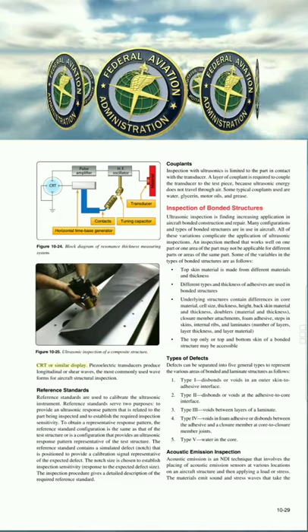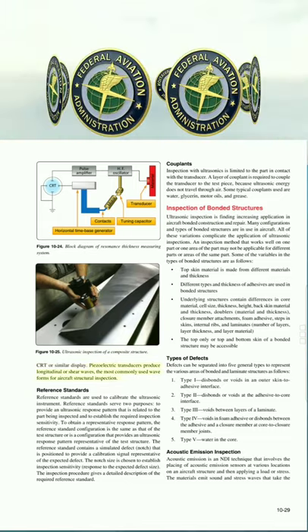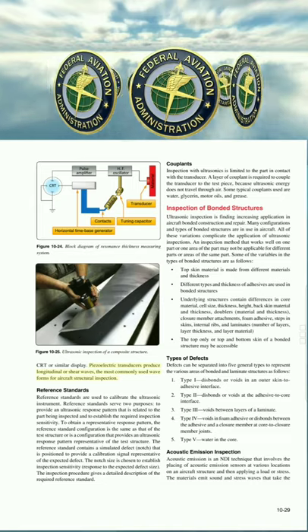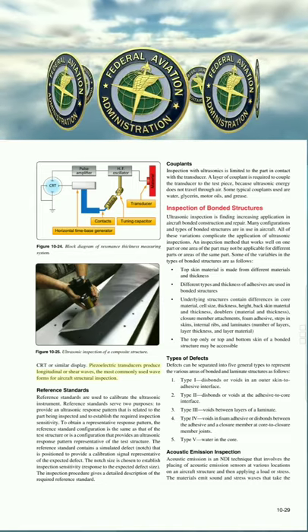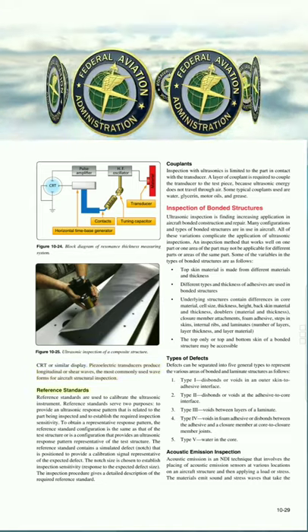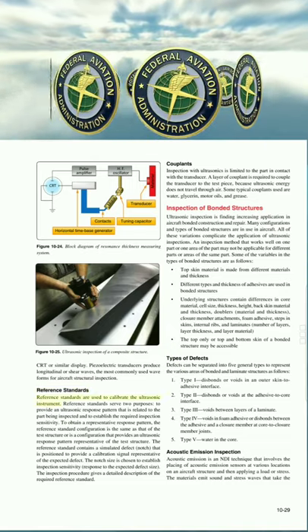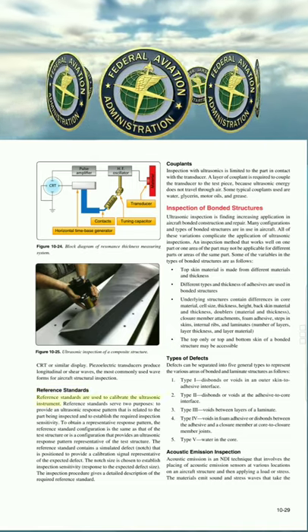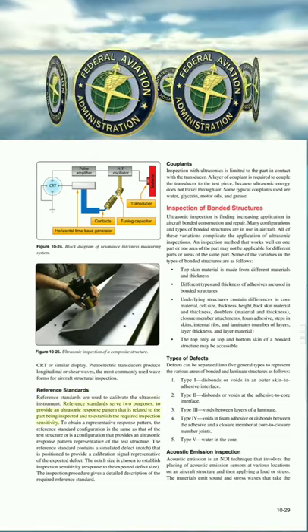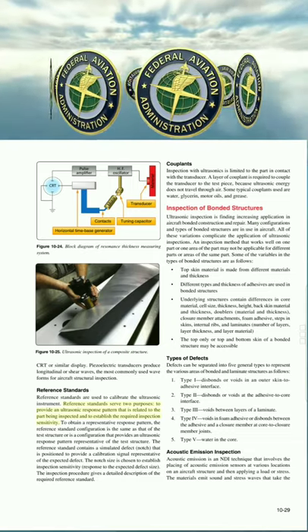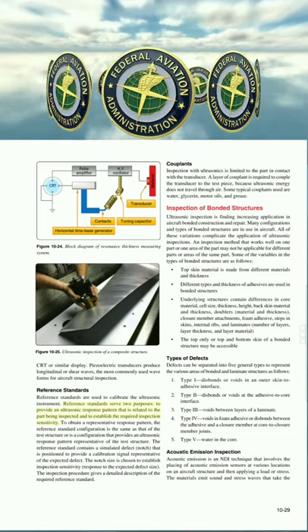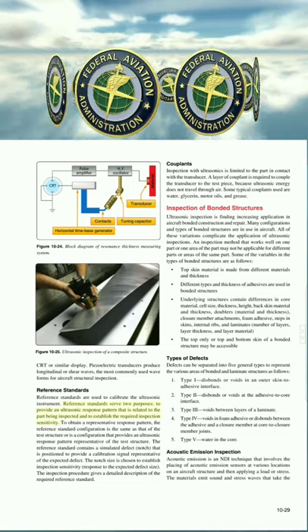CRT or similar display. Piezoelectric transducers produce longitudinal or shear waves, the most commonly used waveforms for aircraft structural inspection. Reference standards. Reference standards are used to calibrate the ultrasonic instrument. Reference standards serve two purposes: to provide an ultrasonic response pattern that is related to the part being inspected and to establish the required inspection sensitivity.